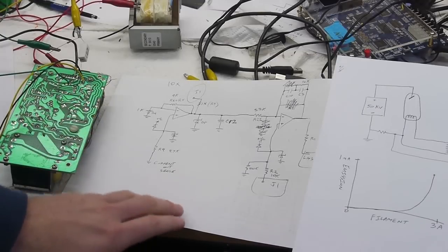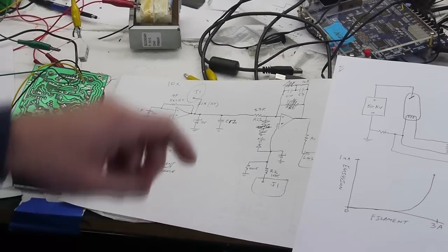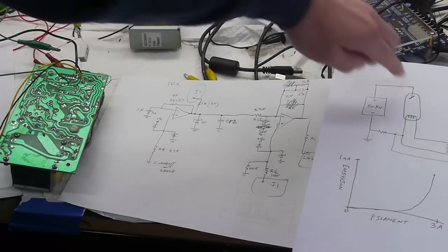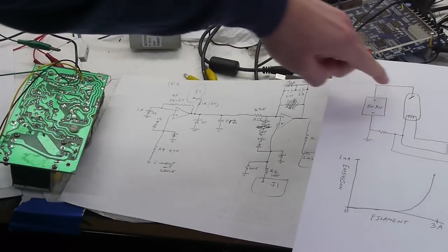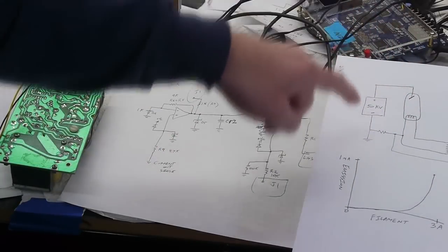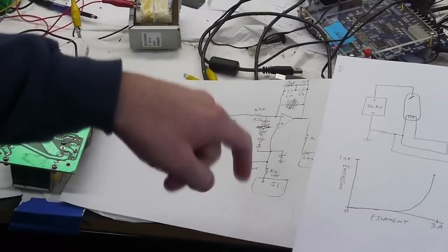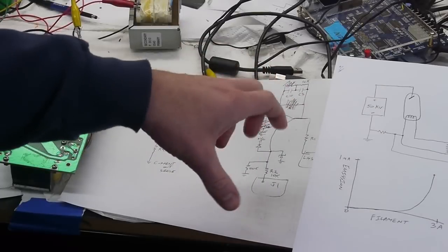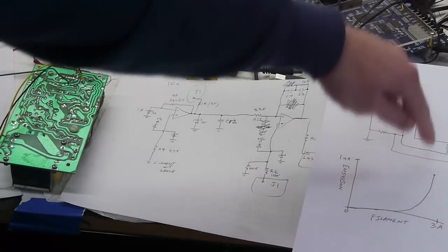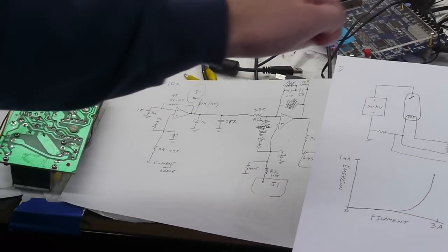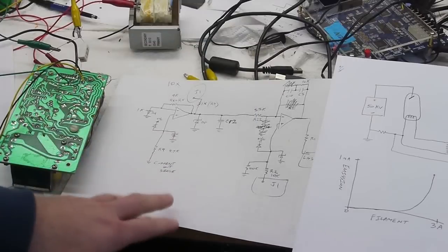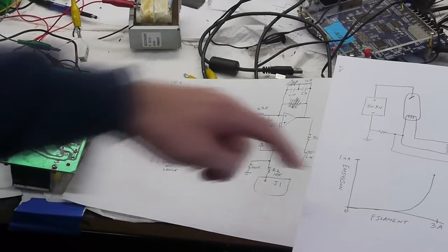So the point of this circuit is to measure the amount of emission current going through the tube and then adjust the amount of filament current to achieve a specific emission. And since we have this nonlinear relationship here the circuit has to be closed loop and quick reacting so that you don't get a runaway condition.